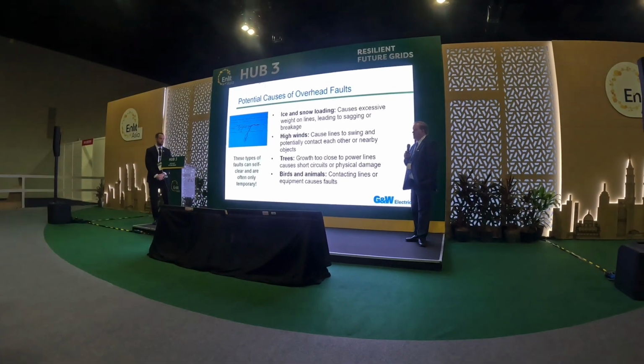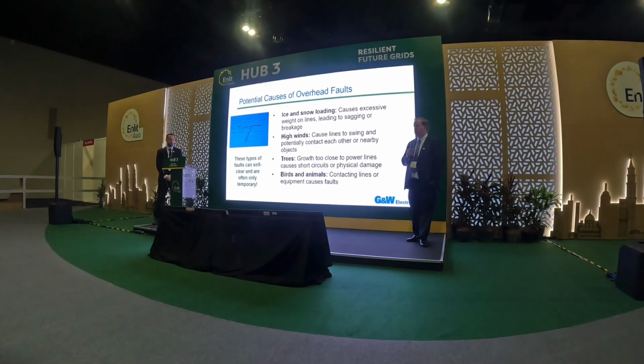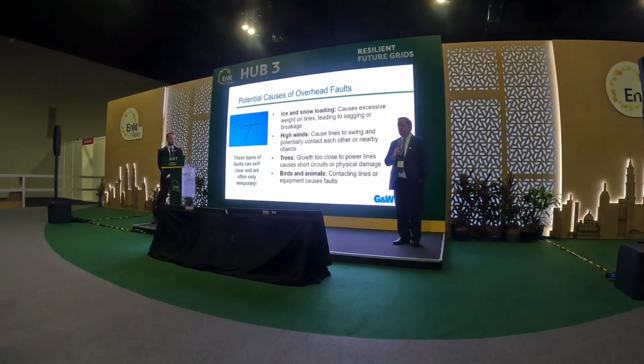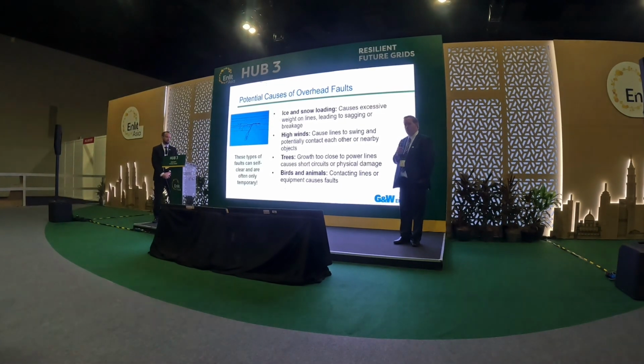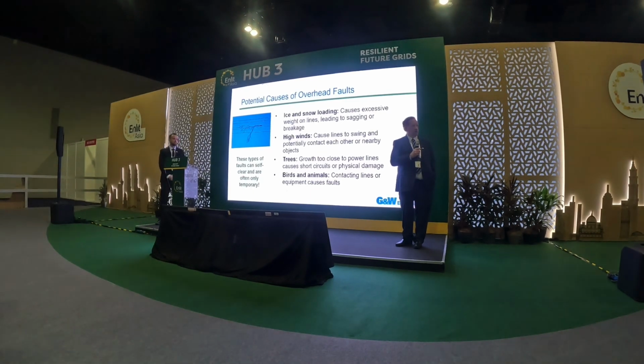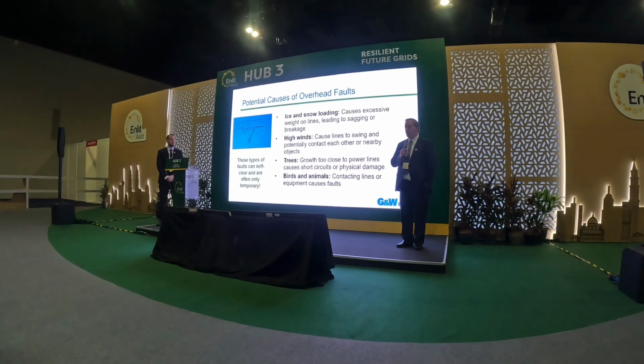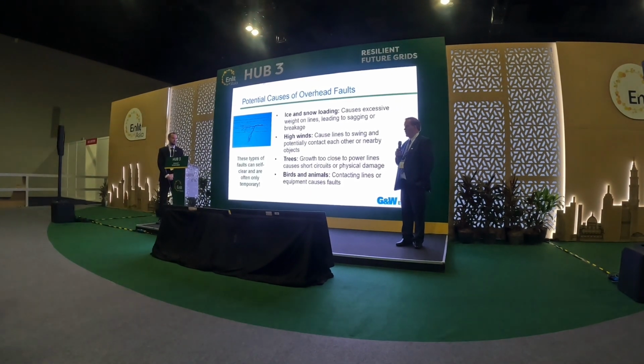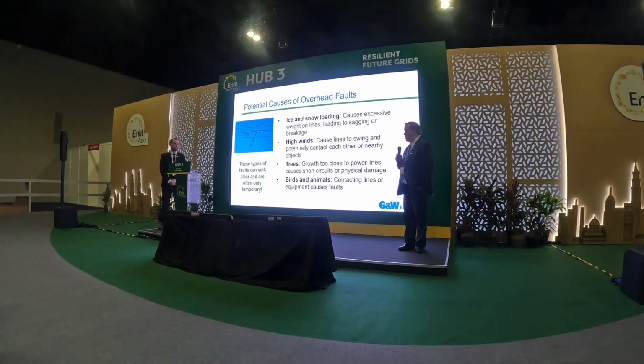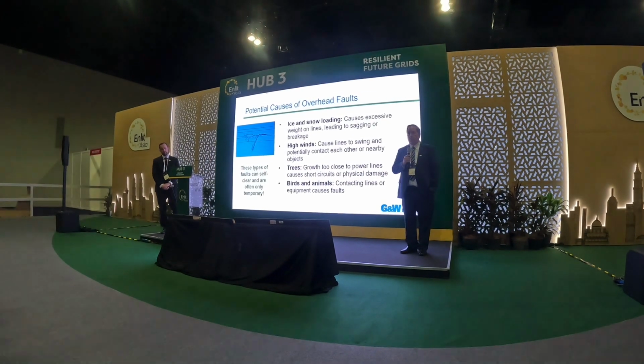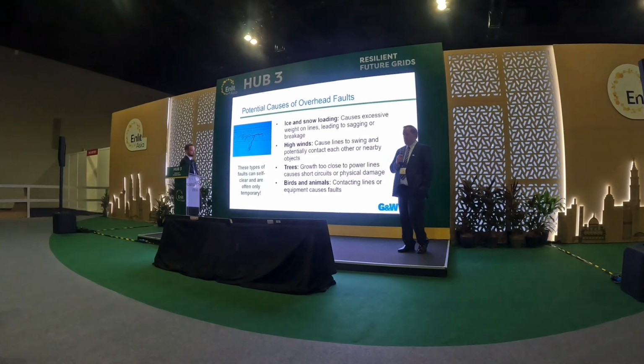You can have high winds. These high winds, depending on the cable tension, might allow the cables to swing and touch one another. Well, clearly that's going to self-heal and clear, and so by using an automatic circuit recloser, you can avoid having that result in an outage that would have occurred if the substation breaker had to trip, for example.